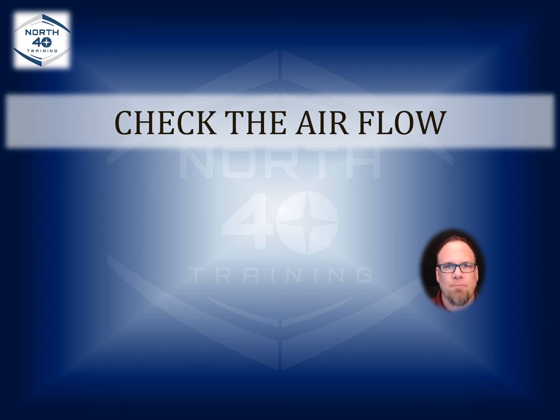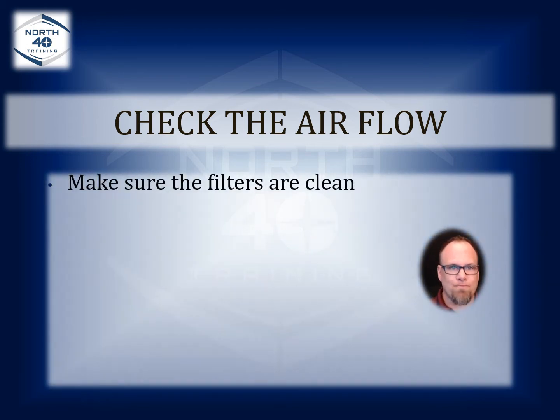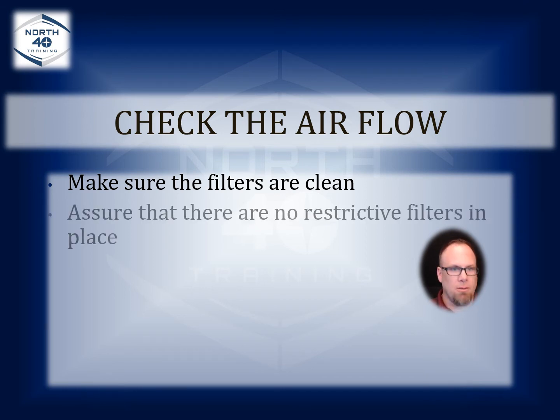So in looking at airflow, there's a couple of things you've got to think about. First of all, you've got to make sure that the filters are correct. They've got to be the correct filter for the application, the correct size for the application. If either of those things are wrong, it doesn't matter where you have things set. You may not have the proper airflow no matter how you look at it. You've got to make sure that the filters aren't too restrictive.